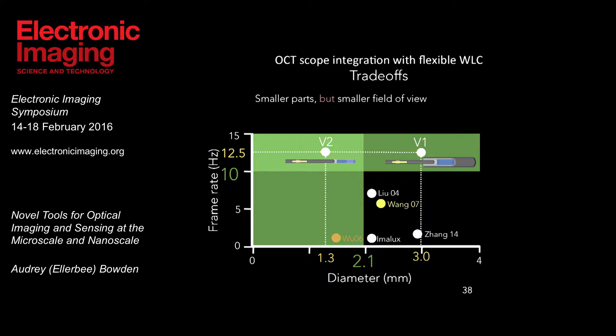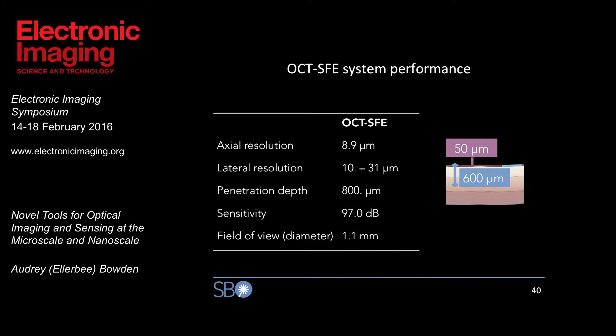To convert the SFE into an OCT imaging scope, we add relevant optics. Our initial version was about three millimeters in diameter, slightly too large for the application. More recently, we've developed a smaller version that meets the correct size requirements. Our current version 2 scope has hope of fitting into the clinical cystoscope. The system has an axial resolution of about 9 microns, sufficient to distinguish the boundaries of these tumors. Most importantly, it has a penetration depth of about 800 microns, which allows us to see into the muscularis layer — where the clinical distinction for treatment occurs.